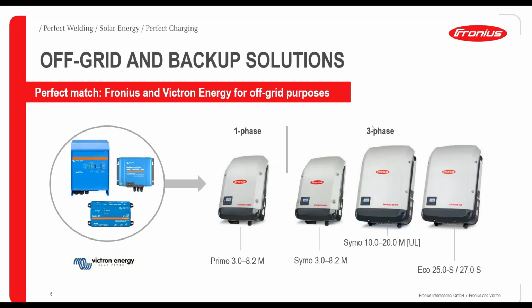On the three-phase side, we are fully compatible with our small Symo, again from 3 to 8.2 kilowatts dual tracker inverter. For bigger applications, when the system size gets bigger, we also have the correct products for a perfect match between Fronius and Victron: the Symo up to 20 kilowatts, and the Eco, our cost-optimized project inverter, to a max of 27 kilowatts with a single tracker.